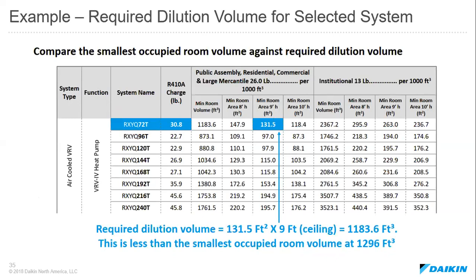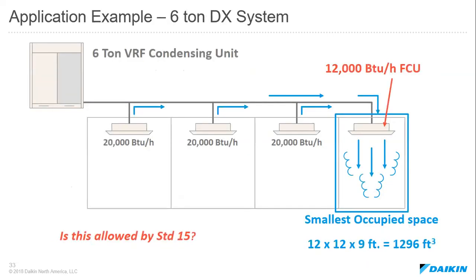Next, we'll look at the required dilution volume. In other words, what's the minimum size space to which that indoor unit could be applied. In this case, that space is 131.5 square feet times a 9-foot high ceiling. So that means our smallest space is 1183.6 cubic feet. Because our space itself is larger than 1183 cubic feet, we're at 1296 cubic feet. In this example I showed you here, this would be acceptable and allowed by ASHRAE Standard 15.